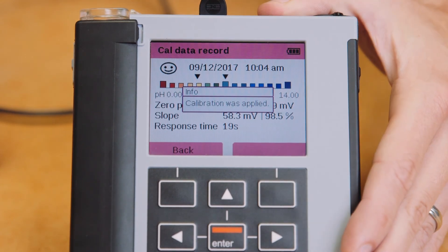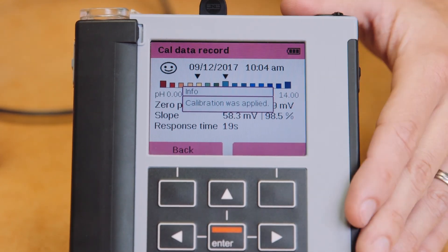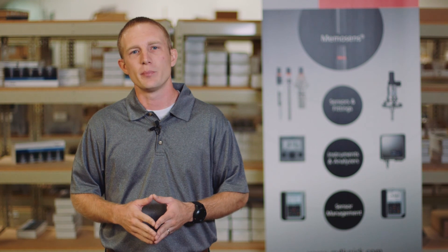We can now press Apply, which writes the calibration data to the Memosens sensor head, or Discard to begin the process again. This completes the offline calibration process of our Memosens pH sensor. As you can see, the entire procedure took less than two minutes and was done conveniently right here in our workshop. This sensor can now be stored on the shelf with the rest of our pre-calibrated Memosens sensors, ready for field exchange at a moment's notice. Thank you for watching.